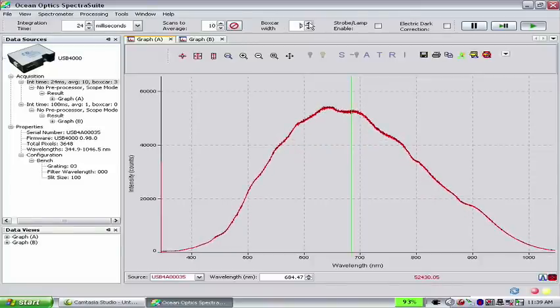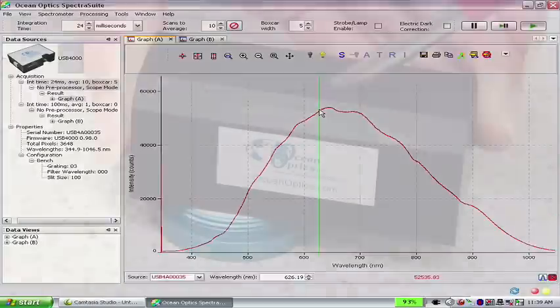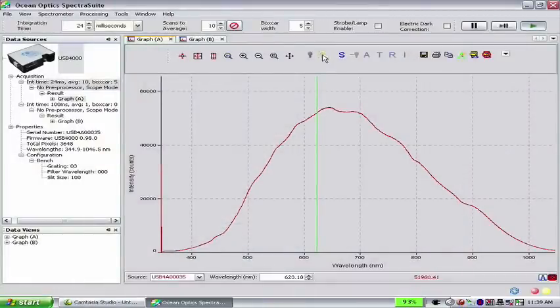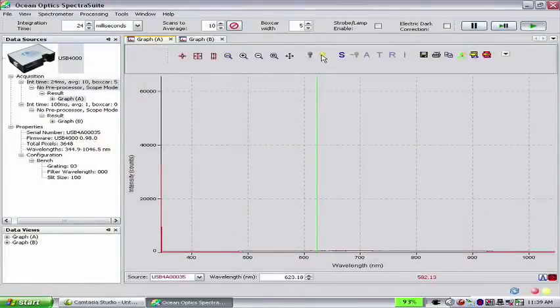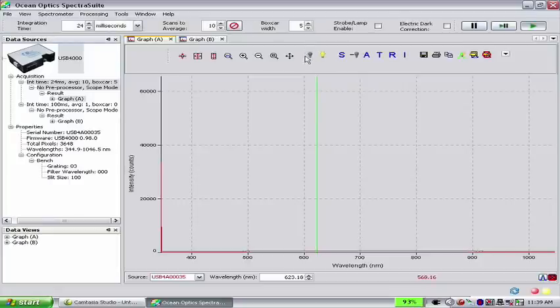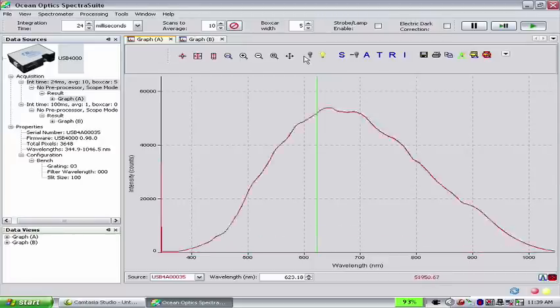Click on the spectrum graph to activate the icons. Now with the RPH1 on the standard and the shutter open, click the Store Reference Spectrum or yellow lightbulb icon. This stores the reference spectrum. With the shutter closed and the RPH1 still on the standard, click the Store Dark Spectrum icon. Once you have stored the reference and dark spectrum, you should see the Process Mode icons activate. Now open the shutter.